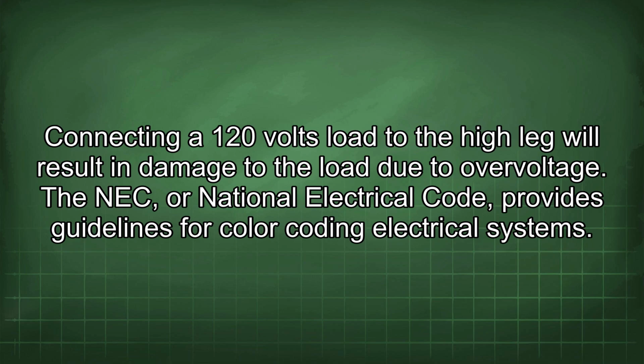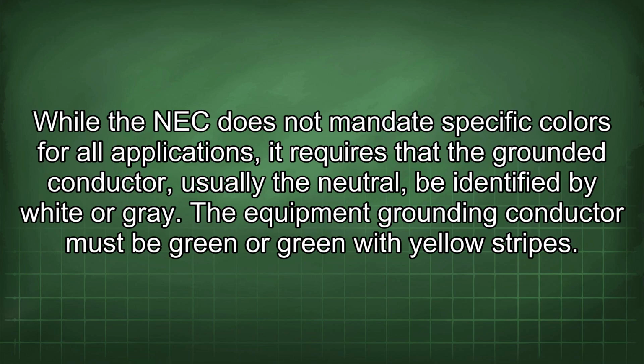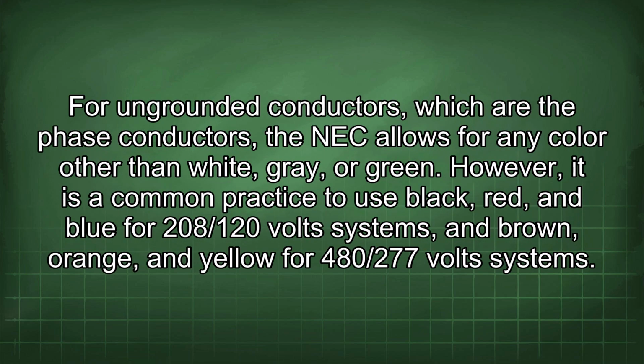The NEC, or National Electrical Code, provides guidelines for color coding electrical systems. While the NEC does not mandate specific colors for all applications, it requires that the grounded conductor, usually the neutral, be identified by white or gray. The equipment grounding conductor must be green or green with yellow stripes. For ungrounded conductors, which are the phase conductors, the NEC allows for any color other than white, gray, or green.